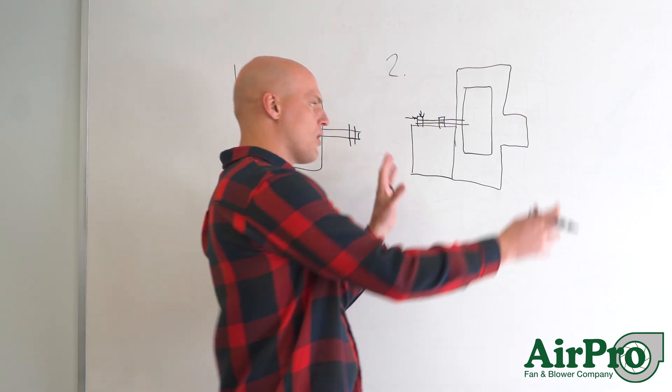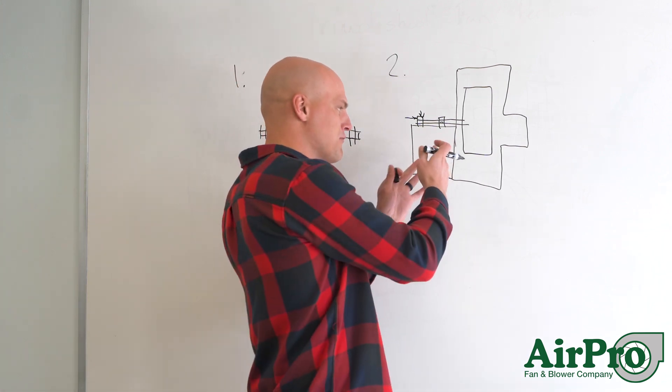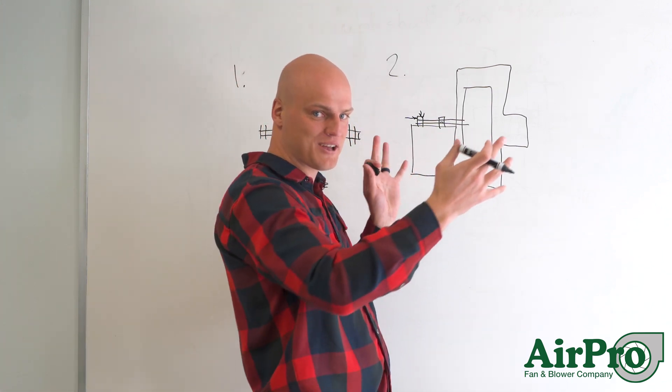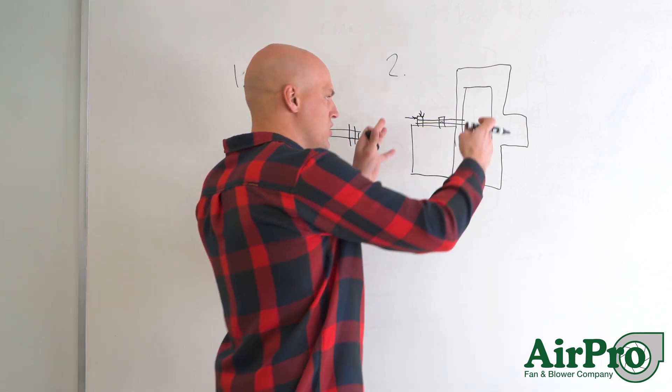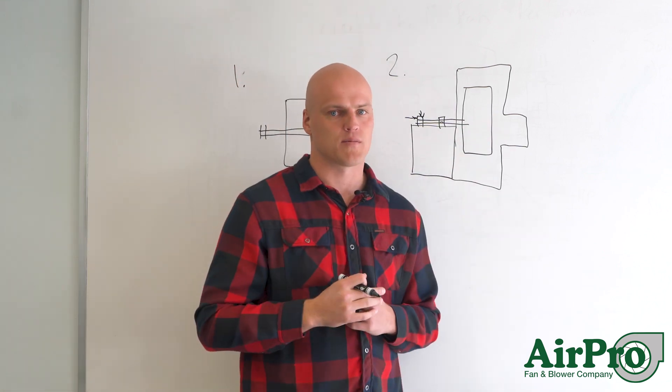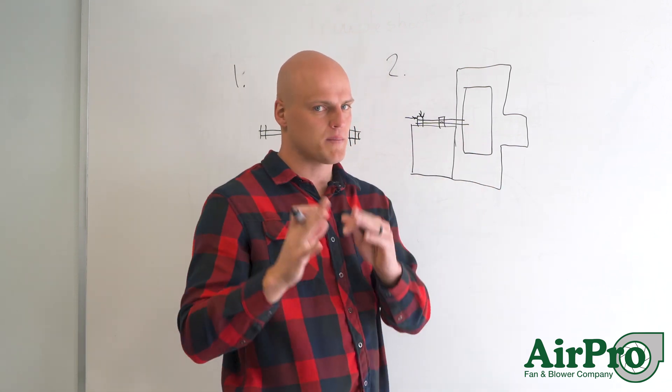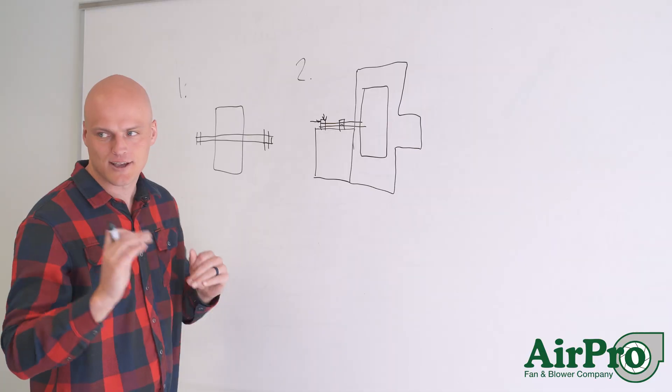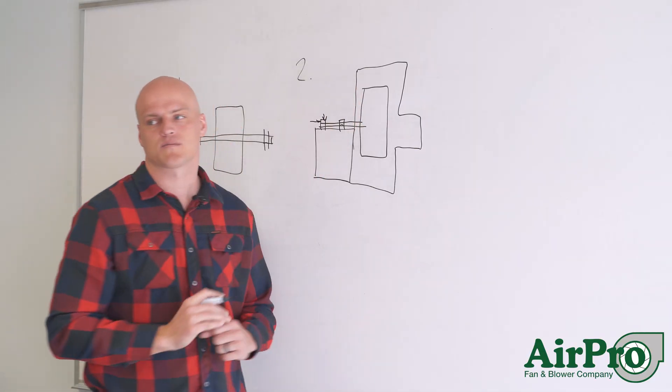But when you put the whole system together, sometimes there are variabilities with how the whole fan comes together to where even a really balanced wheel, you run it over here and you're still over the vibration limit you need to be at. So once you're over here, usually the balance is not nearly as severe as what you have to do over here. But you'll still have to do some tweaks to the wheel.